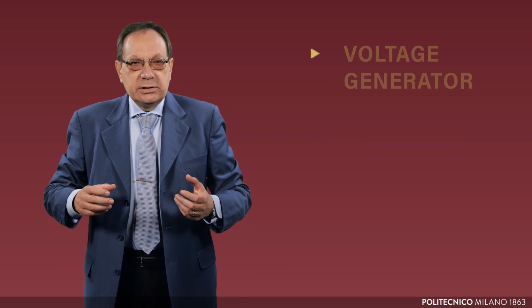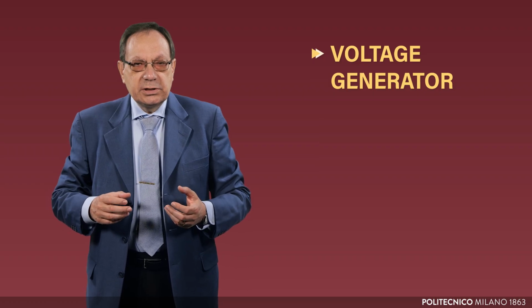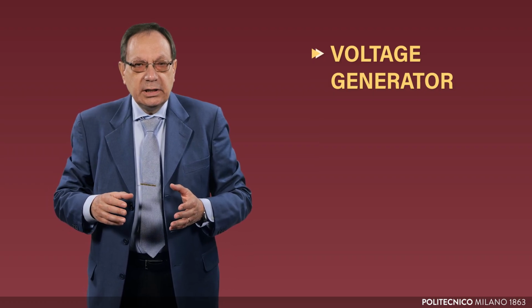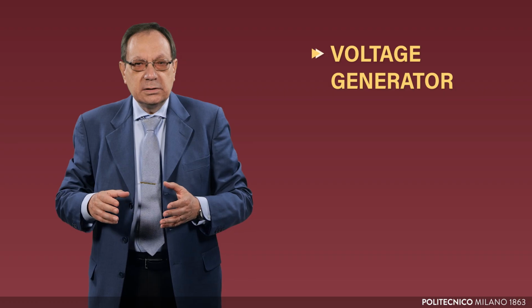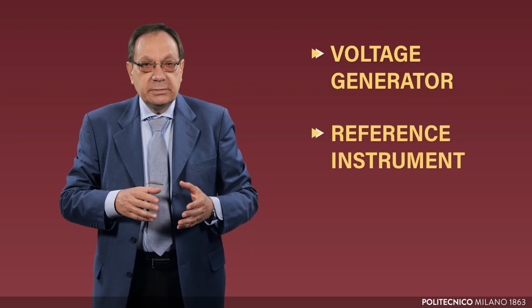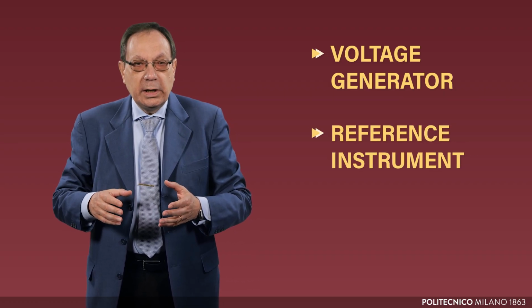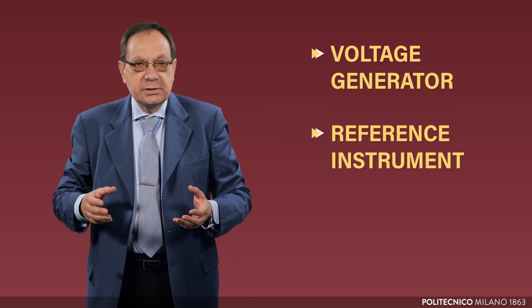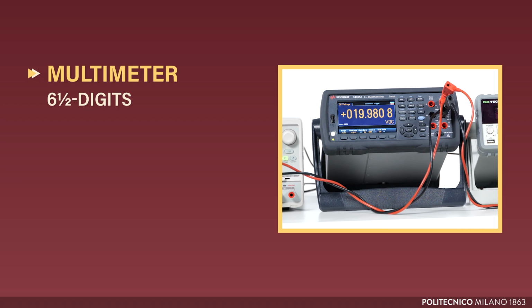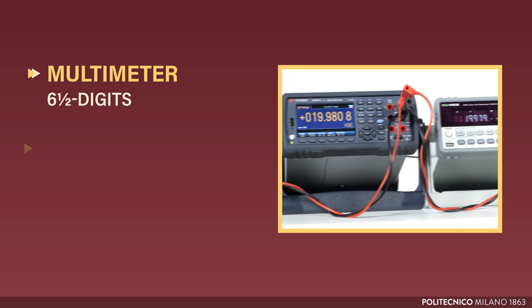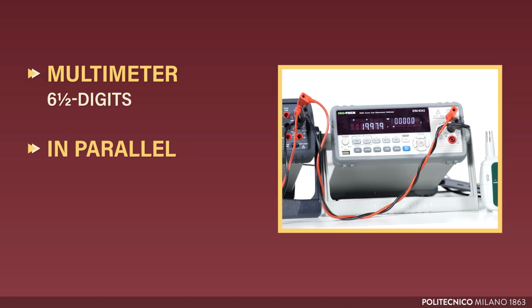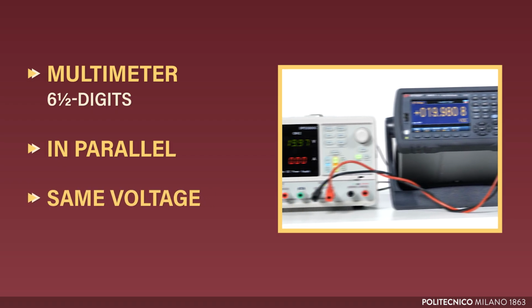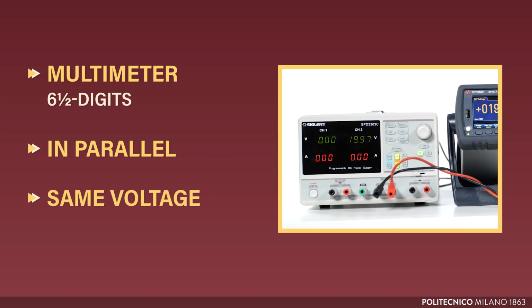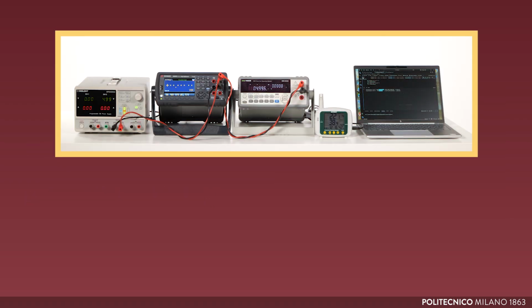We need a voltage generator capable of producing various voltage values within the range from 0 to 20 volts, as well as a reference instrument that is more accurate than the one to be calibrated, which serves as the reference standard. For this purpose, we use a 6.5-digit multimeter connected in parallel to the instrument to be calibrated, so that it measures the same voltage generated by the voltage generator. Here you can see these 3 devices already connected.